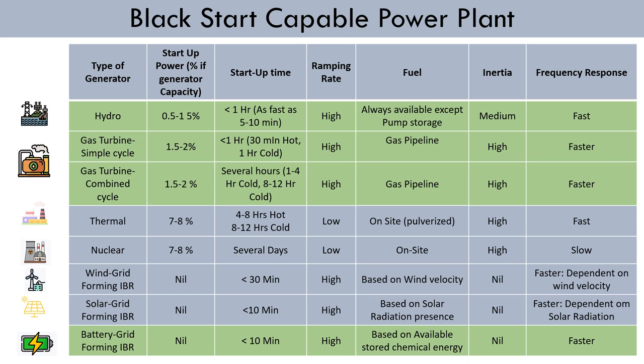Moreover, thermal power plants rely on continuous fuel supply, which may be disrupted during a blackout, while nuclear power plants have complex and time-consuming startup and shutdown processes. Furthermore, thermal and nuclear power plants require a stable and synchronized grid connection to operate efficiently, making it difficult for them to independently start up and stabilize the grid during a blackout. Despite their limitations as black start capable plants, thermal and nuclear power plants still have a crucial role as baseload power in ensuring long-term grid stability once the power system has been restored by other black start capable resources.